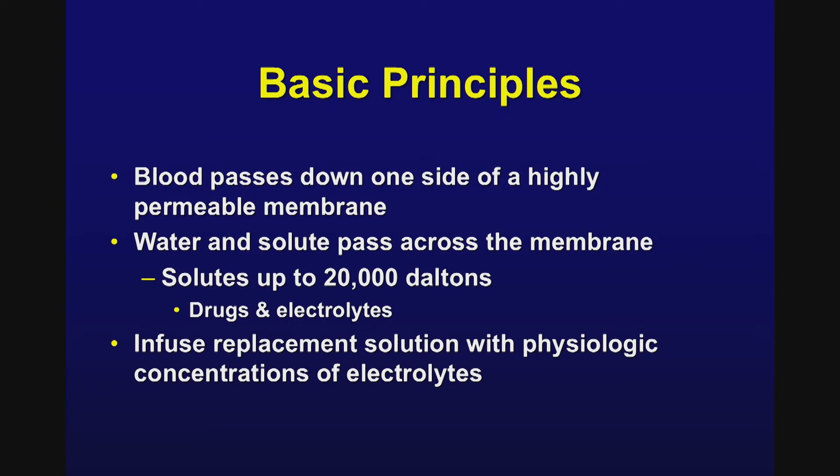The basic principle is that blood passes down one side of a highly permeable membrane, and water and solute pass across the membrane into an ultrafiltrate collection vessel. Solutes up to 20,000 Daltons can easily be removed via CRRT. Most drugs and electrolytes are within this range, so they're easily removable during this process. Replacement solutions with physiologic concentrations of electrolytes can be infused to keep the patient relatively stable from a metabolic standpoint.